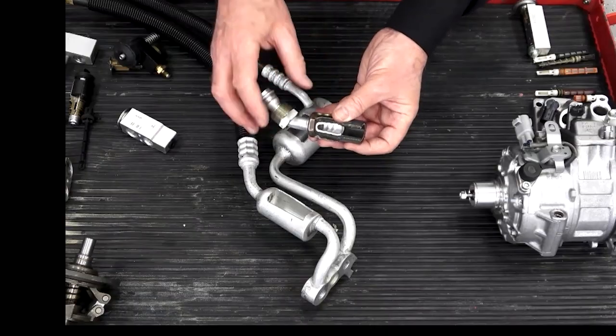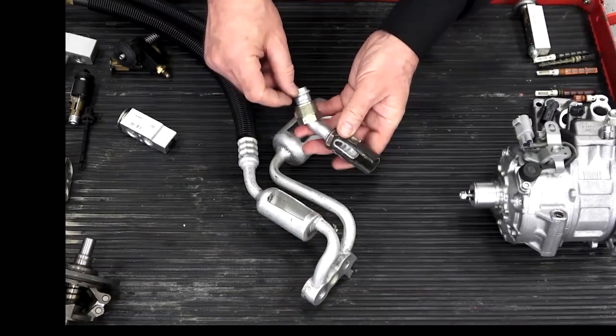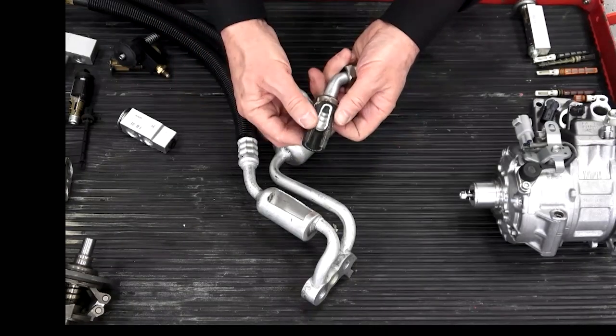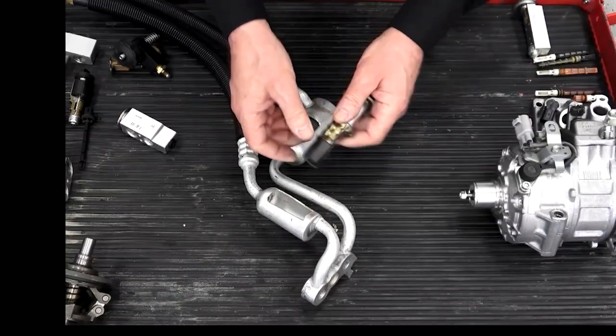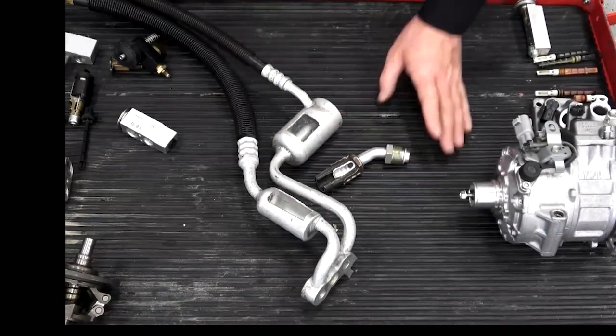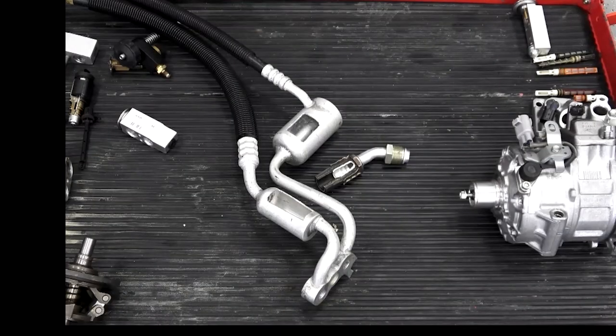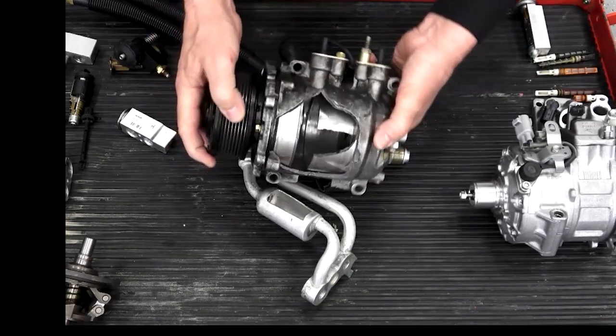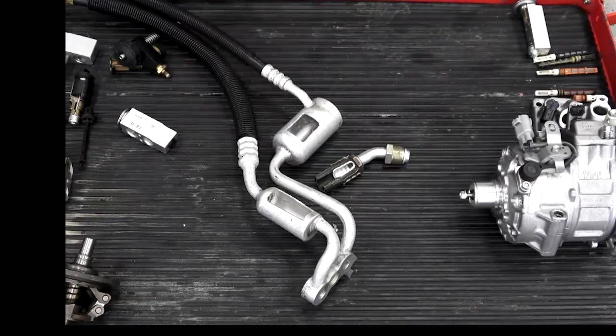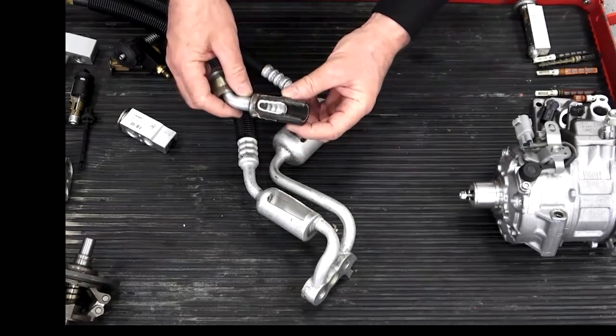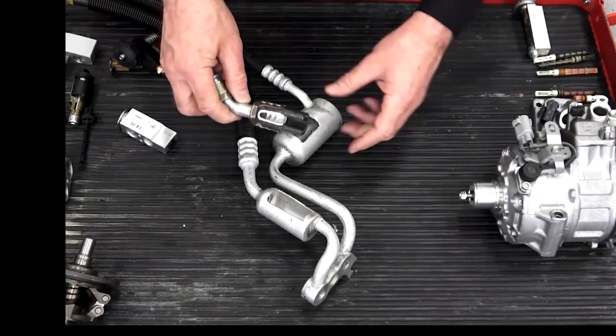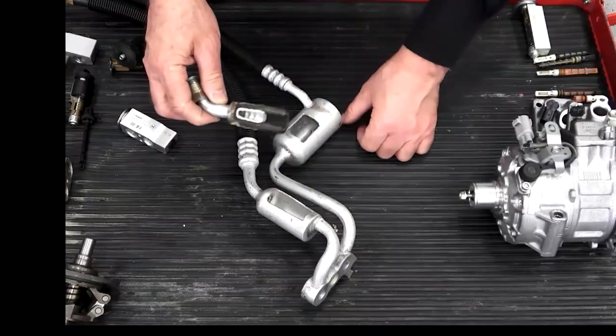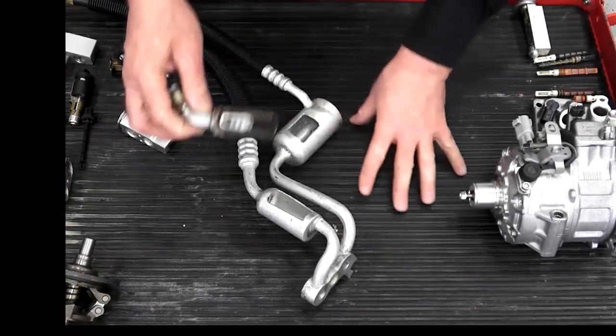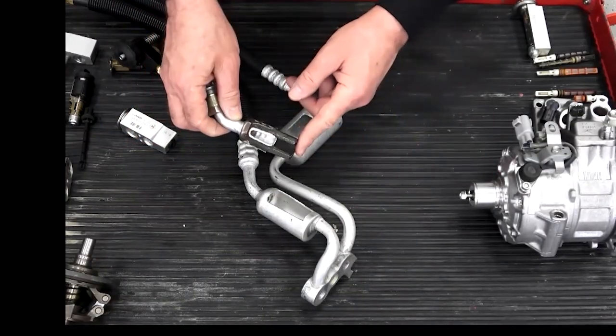And so honestly, when you count the cost of the flush, the cost of your time to do the flush, and the fact that you're flushing a 10-year-old hose, and the compressor came in with a hole in the side like this here, when are you going to be able to pressure test this system? When you've done the entire repair, evacuated and recharged it, and then right at the end of all of that, you find you have a leak. Often it is literally cheaper to replace the hoses at the outset than to be trying to leak check, or flush, a 10-year-old hose that you don't even know is leaking yet or not.